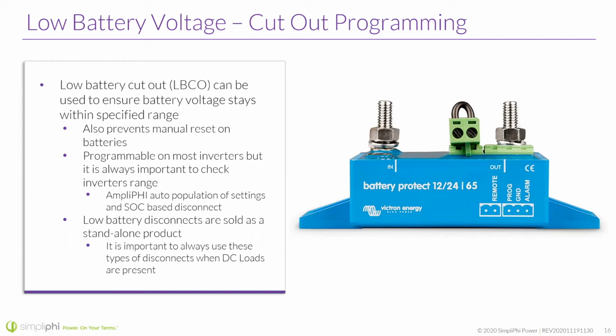Some of the older inverters might not be able to hit that. They might be set for lower. They're used to lead acid batteries. Lithium wasn't even around when they were created, or at least it wasn't being utilized. So oftentimes you want to double check that with older equipment.